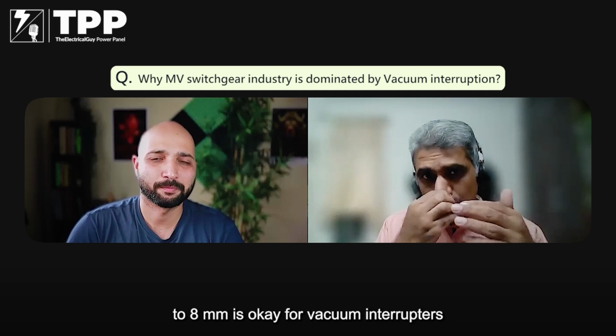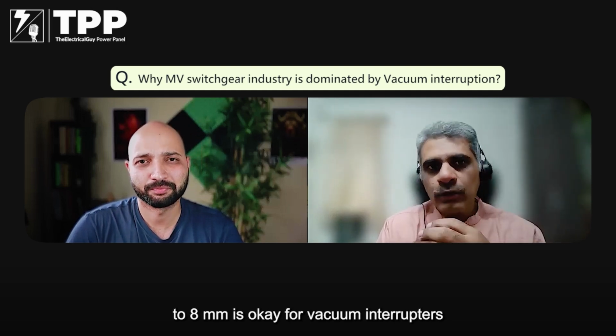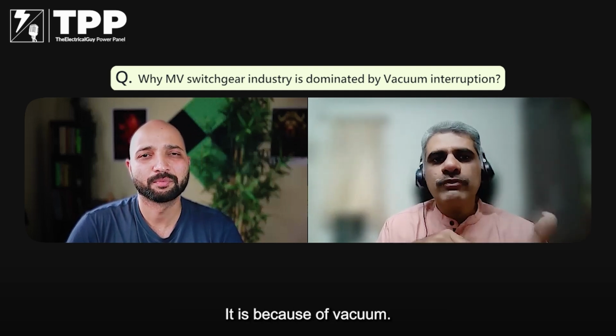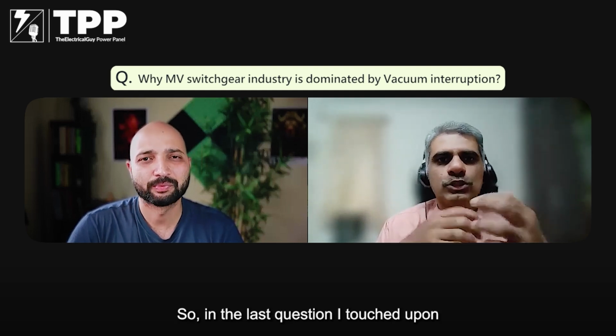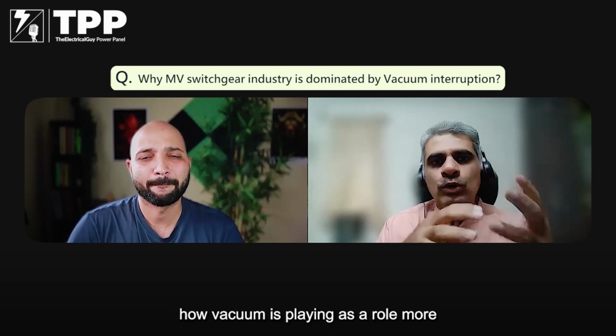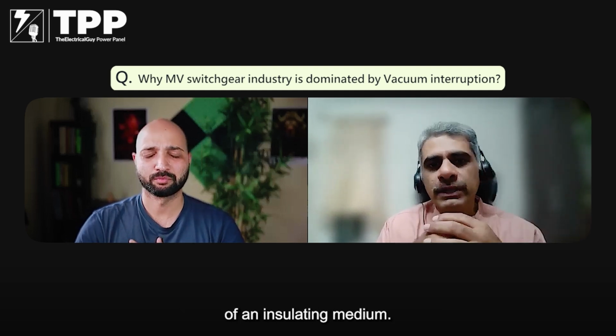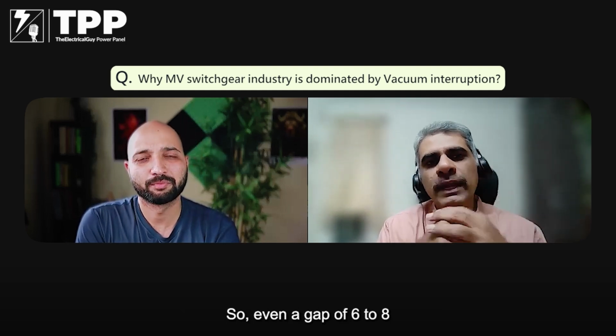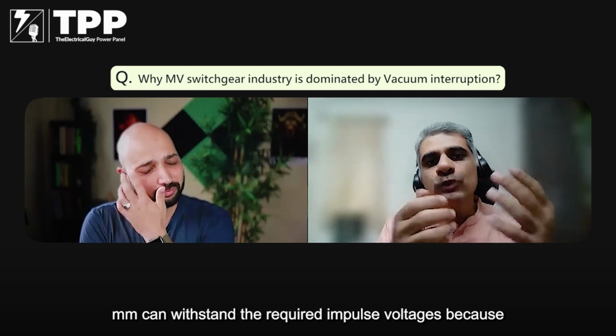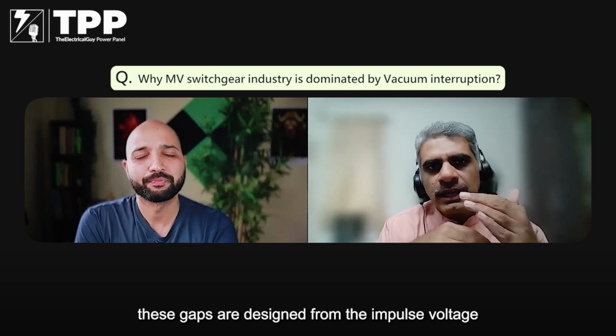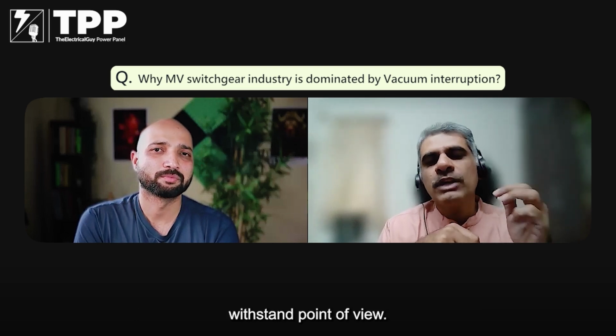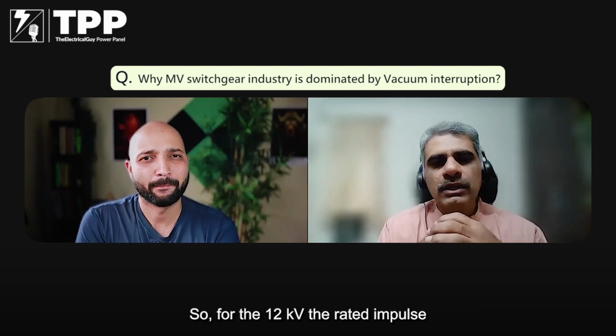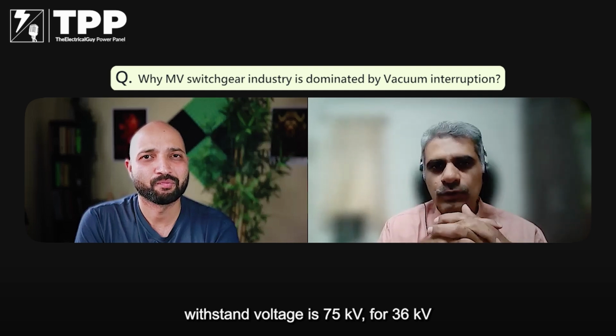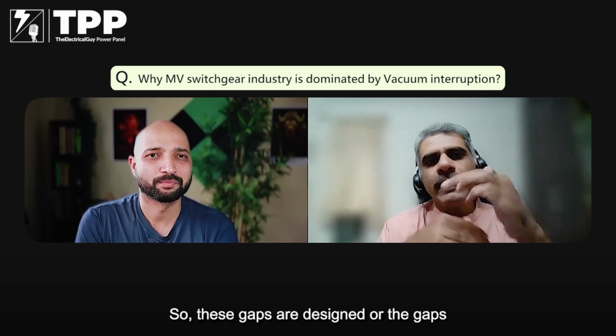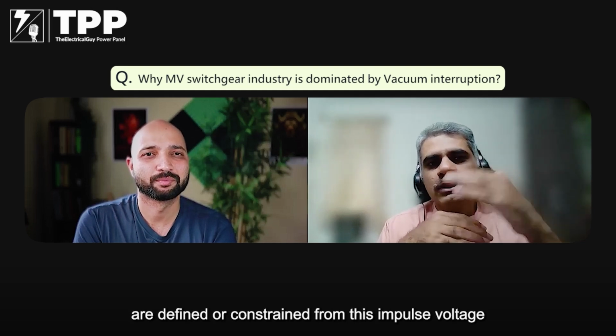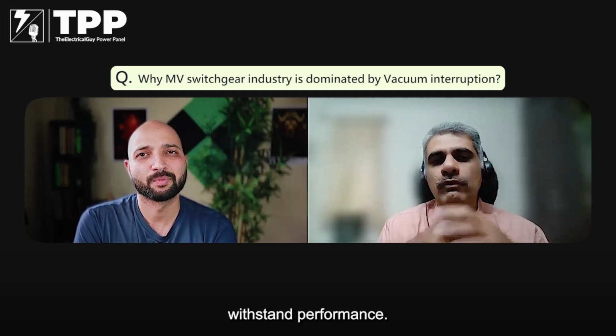And why is 6 to 8 mm okay for vacuum interrupters or vacuum breakers? It's because of vacuum. In the last question, I touched upon how vacuum plays a role more as an insulating medium. So even a gap of 6 to 8 mm can withstand the required impulse voltages, because these gaps are designed from the impulse voltage withstand point of view. So for a 12 kV, the rated impulse withstand voltage is 75 kV. For 36 kV, it is 170 kV. So the gaps are defined or constrained by this impulse voltage withstand performance.